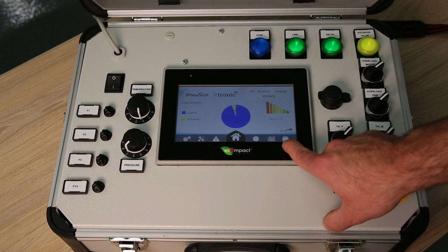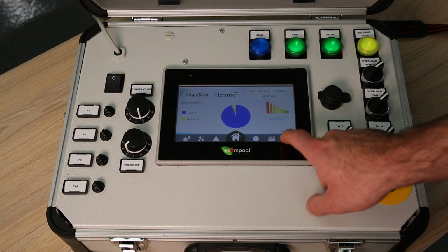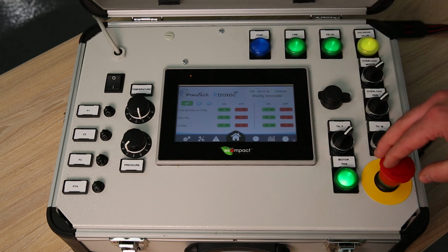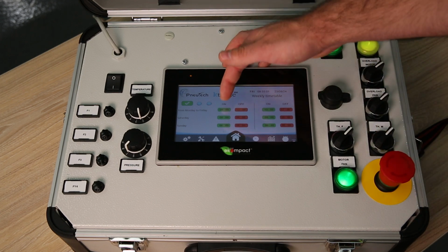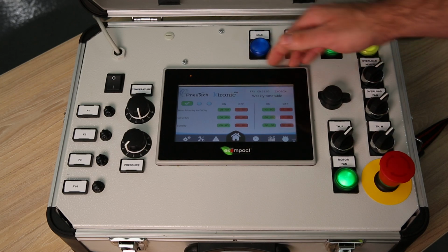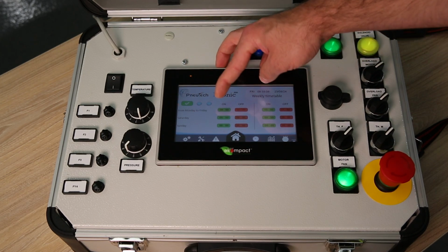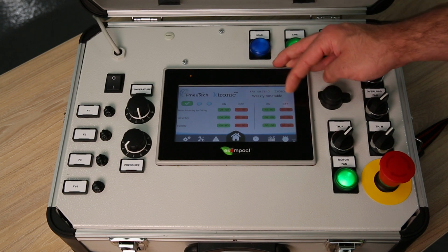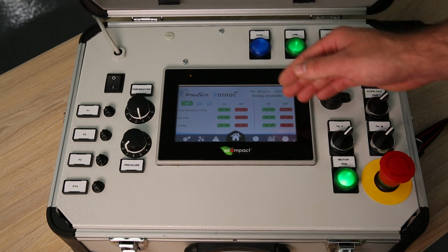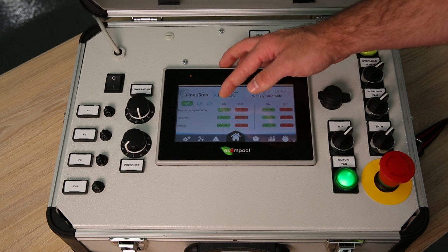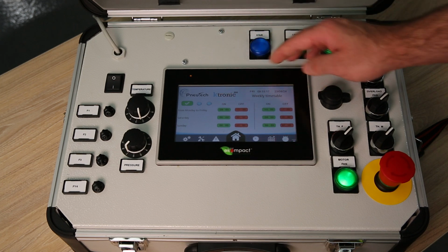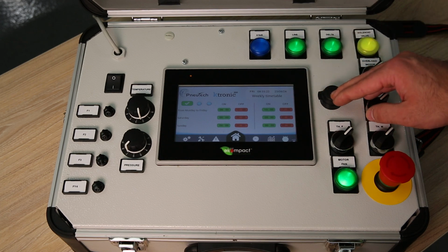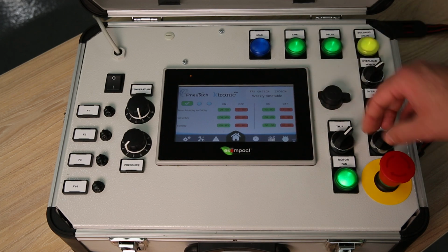Okay, going to the little stopwatch setting in the bottom right, we will find the timetable setting. What this setting here can do, we'll look at the example that's already set in the controller. From Monday to Friday, we have on set to 8, off set to 12, on set to 13, and off set to 17. What that means is this compressor will turn on at 8 in the morning, turn off at 12 for 1 hour to turn back on at 1 p.m., and then turn back off for the end of the day at 5 p.m.